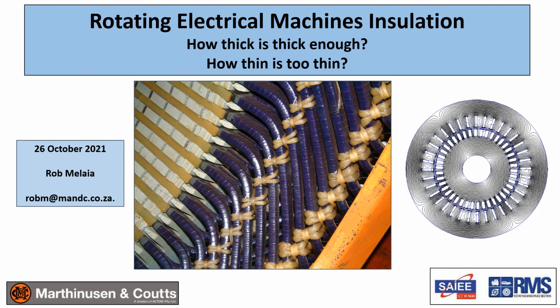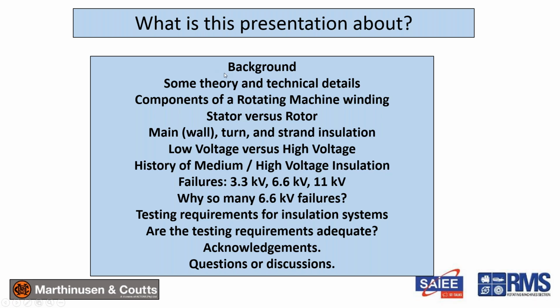So let's get on. Just the background I've mentioned, some theory and technical details, and we need to look at the components of a rotating machine winding before we can conclude or analyze insulation. In that respect, there are stator and rotor windings. Obviously, in squirrel cage induction motors, without insulated cages, the insulation doesn't apply. But rotor insulation is actually a lot more common than we think. It's on wound field in synchronous motors, as well as wound rotor induction motors, and for that matter, DC armatures.